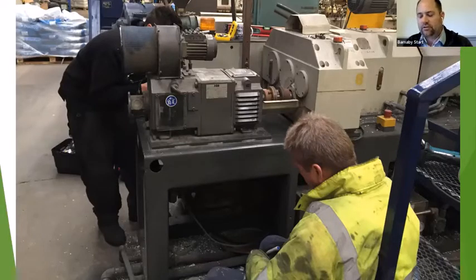Just check with the manufacturer if we're going to do that, just make sure it's okay to do that. A lot of motors are balanced beyond their working speed anyway, and at this sort of power they tend to be well dynamically balanced anyway. So you can run above that sort of base speed. Remembering also, if you're running above base speed, you will sacrifice your torque. So usually there's a trade-off for getting the speed out of the motor against the actual output torque.